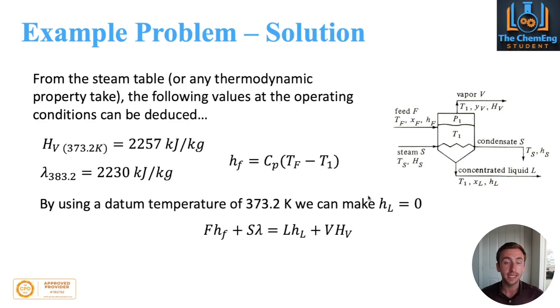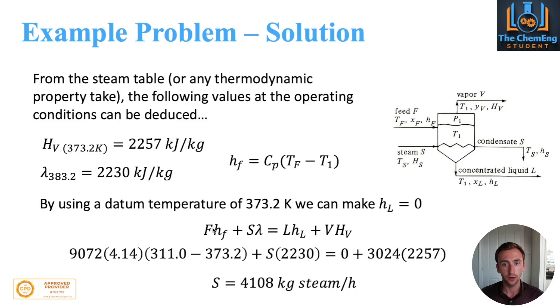Taking whatever datum temperature you want can really simplify the equations. All it will influence is the values of the physical properties. Now from here, all you have to do is substitute in the values into this equation, and we work out that the amount of steam required for this operation is 4108 kilograms per hour. So that's the amount of steam that we are going to require.